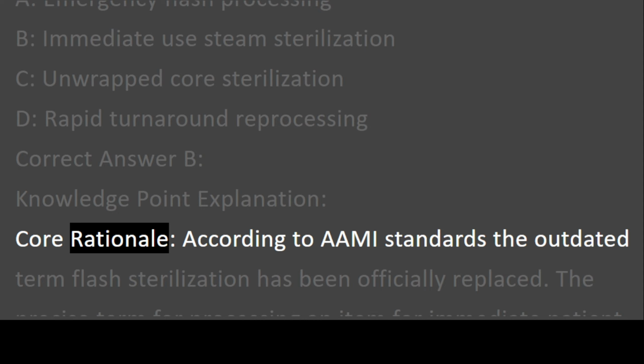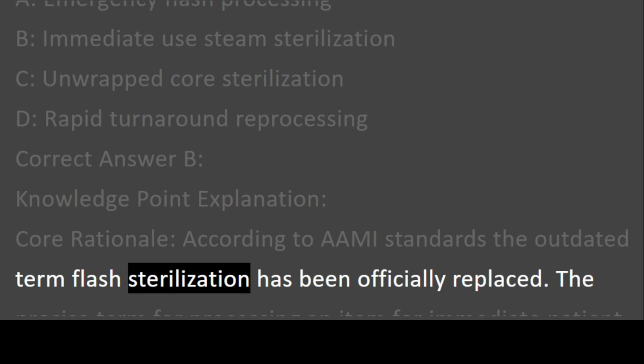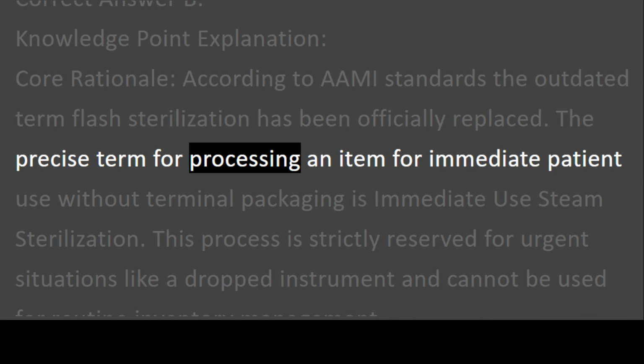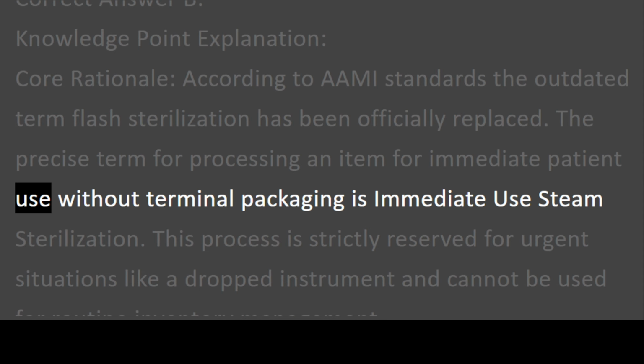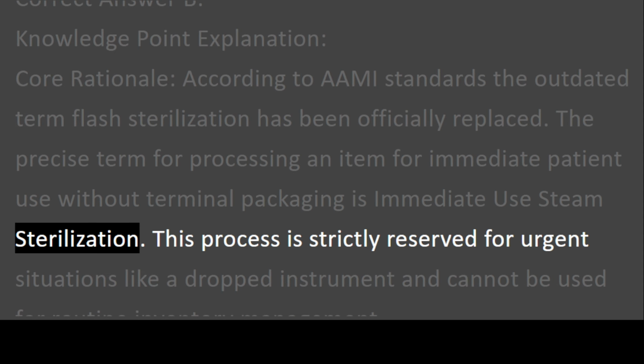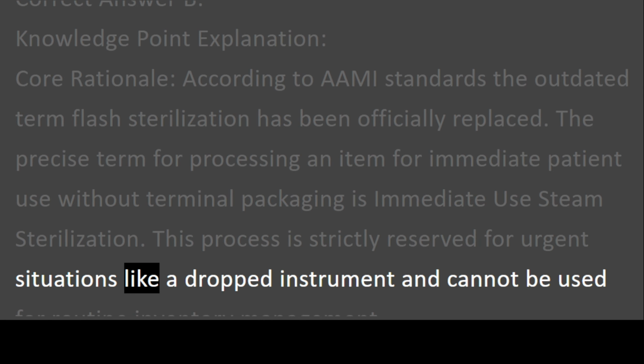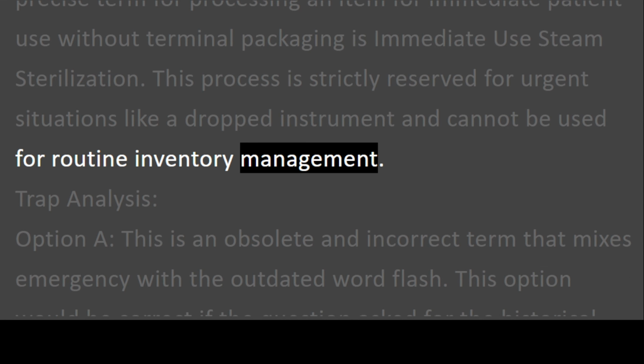Core rationale. According to AAMI standards, the outdated term flash sterilization has been officially replaced. The precise term for processing an item for immediate patient use without terminal packaging is immediate use steam sterilization. This process is strictly reserved for urgent situations like a dropped instrument and cannot be used for routine inventory management.